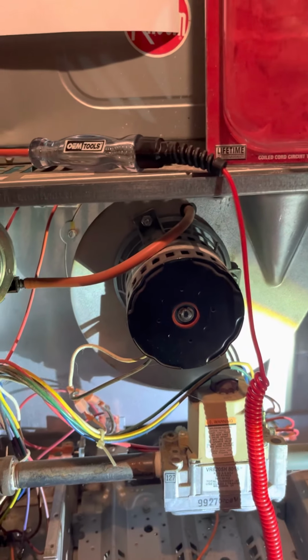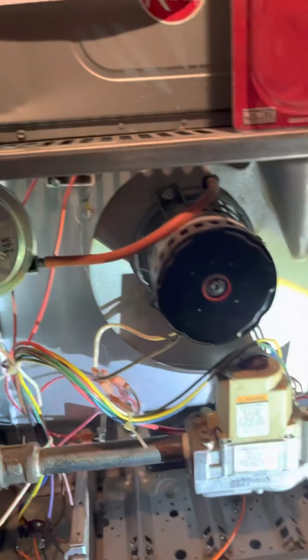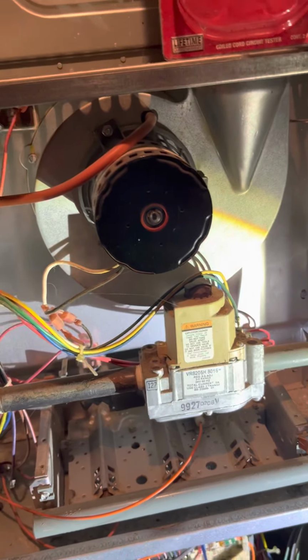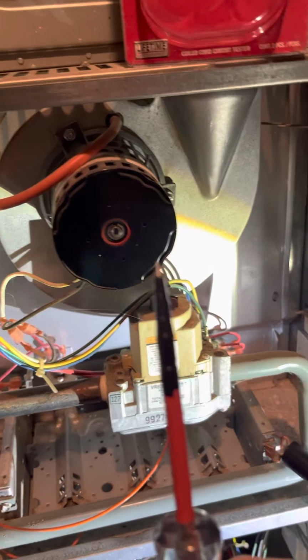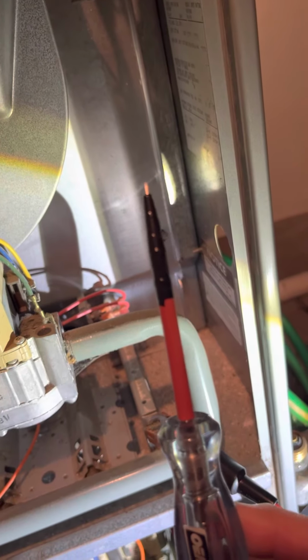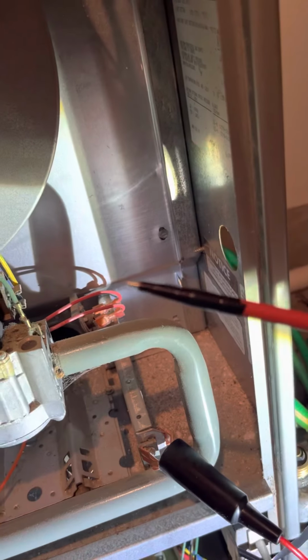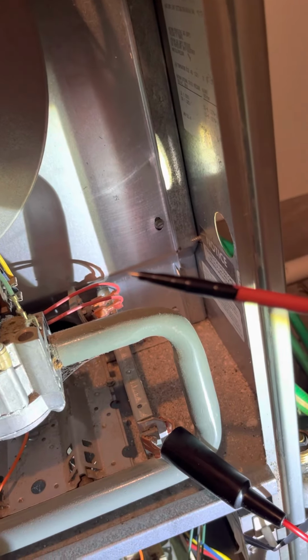So we're going to look real quick at the sequence of operation here. I'm going to take the tester. Oh, I should tell you that you want to make sure that you leave the sleeve on the tester, and you want to tape it so just the tip is showing. As you can see, just the tip of the tester is showing there.